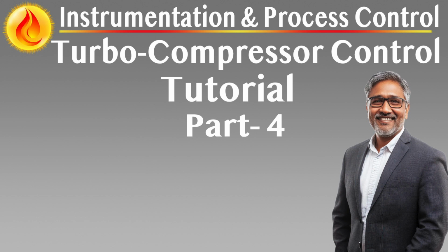Field instrumentation, precision sensing and signal conditioning for reliable compressor control and protection. Overview. The field instrumentation network of the Turbo Compressor Control System, TCCS, serves as the sensory foundation for real-time control, protection, diagnostics, and performance monitoring. Every sensor, transmitter, and field-mounted device is selected, installed, and integrated in line with stringent project specifications and industry standards to ensure accuracy, reliability, and maintainability in demanding process environments.